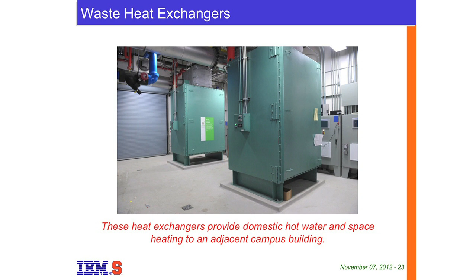These are the exhaust-fired heat exchangers. These are the ones that can be used for providing hot water to the adjacent building. We don't need this for the data center. There are 2 of them, again, 1 per side, and in cases where, in the winter, for example, I may not need all the cooling, I can actually divert the exhaust into one of these heat exchangers and provide hot water to the adjacent building for heating.